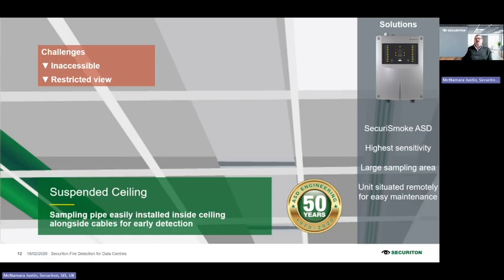Equally, I mentioned briefly we have both suspended ceilings, and we'll look at raised floors in a moment. Historically, and maybe this shows my age, a lot of point detectors might have gone in suspended ceilings, certainly in raised floors. But the big downside, and there are several, is access to provide maintenance post-commissioning once the data center is operational. It's very tricky, difficult, sometimes dangerous, often disruptive if we need to get access to provide maintenance to point detectors either in a ceiling void or in a raised floor.